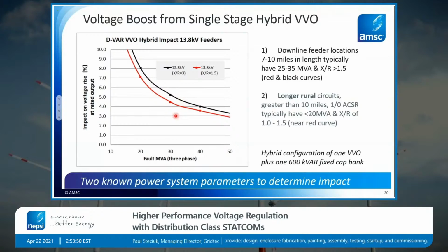So we take that same 30 MVA case. Now we're running at the ability to boost by 5%. So this is very handy for load serving applications in particular. And then that same now longer feeder downline, we're now being able to boost easily in the 8% range. So hybrids are a very cost-effective way to be able to provide more impact from a single STATCOM installation.